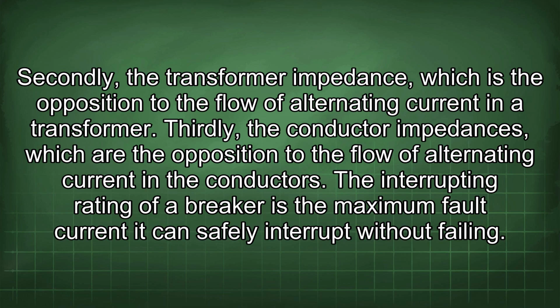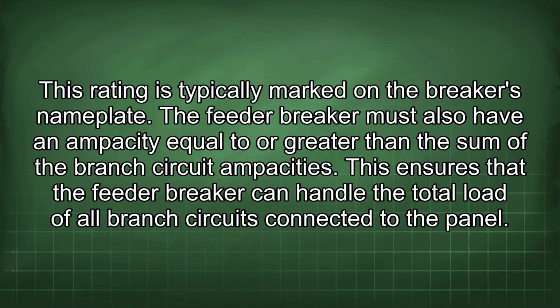The interrupting rating of a breaker is the maximum fault current it can safely interrupt without failing. This rating is typically marked on the breaker's nameplate. The feeder breaker must also have an ampacity equal to or greater than the sum of the branch circuit ampacities. This ensures that the feeder breaker can handle the total load of all branch circuits connected to the panel.